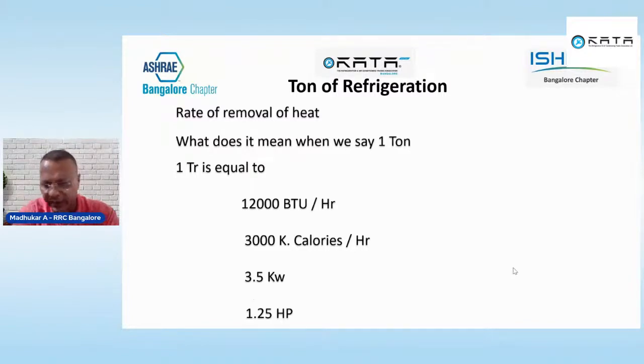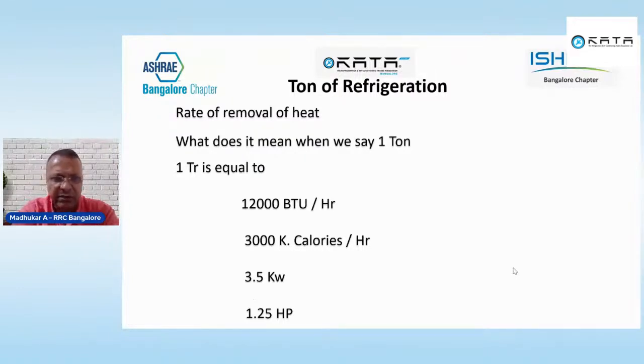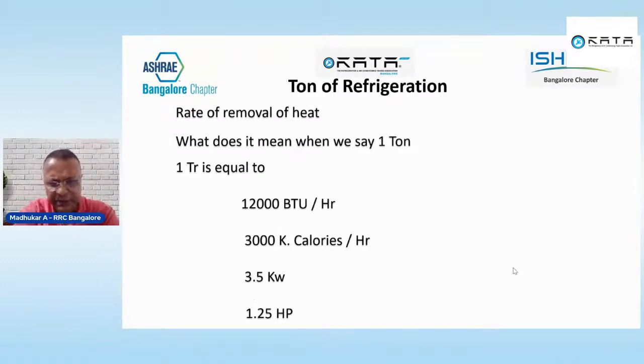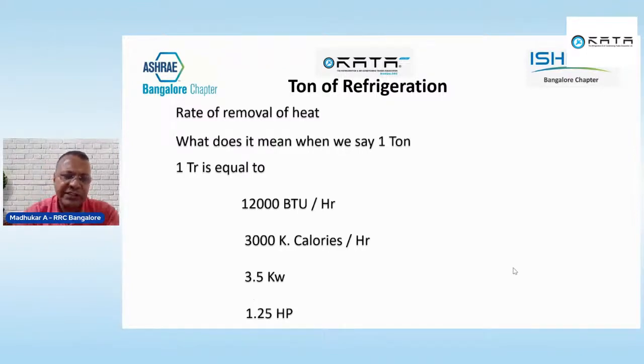One ton of refrigeration equals 12,000 BTU per hour — meaning a 1-ton AC can remove 12,000 BTU of heat in one hour. It is also equivalent to 3,000 kilocalories per hour, 3.5 kilowatts, or 1.25 HP. The kilowatts and HP measurements are generally used in VRF or inverter technology, which is now fast catching up.